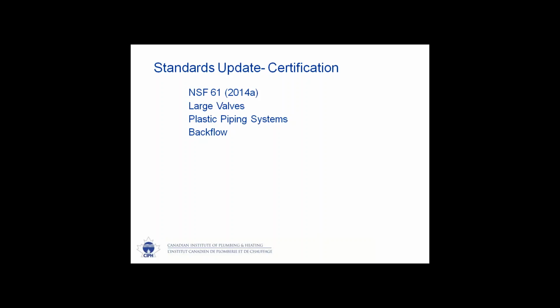Some inspectors have asked the question whether or not the backflow preventers need to be low lead. In the strictest interpretation of the standard, the answer is no, because that version of NSF makes the low lead requirements voluntary until the CSA B64 standard can specify the requirements. Only then can it go live and then get referenced into the code and updated and then become a requirement. But at this point, the interpretation stands that it's not required in Canada at the moment. In a few years, that might change fairly quickly.